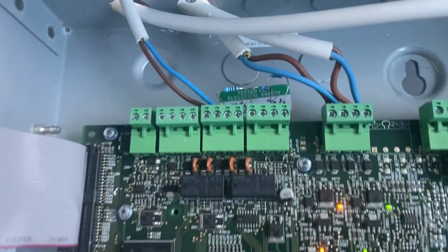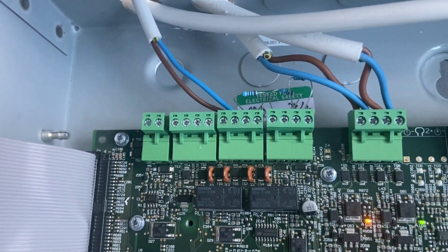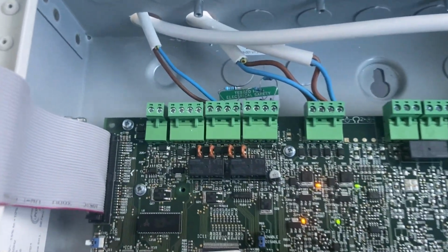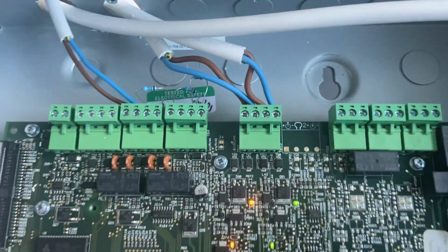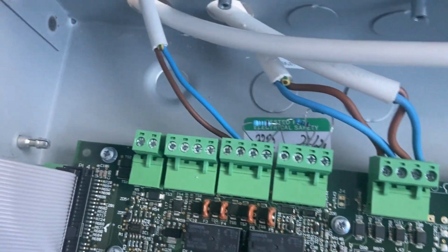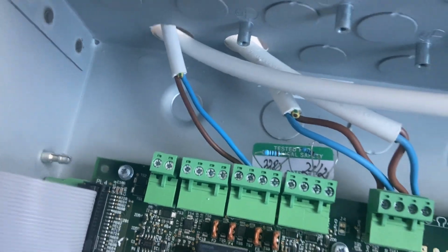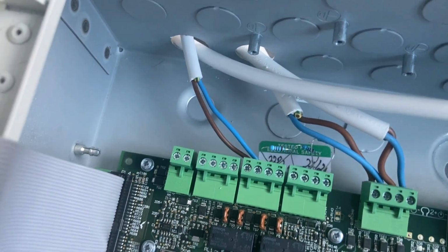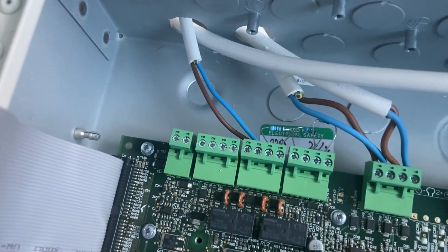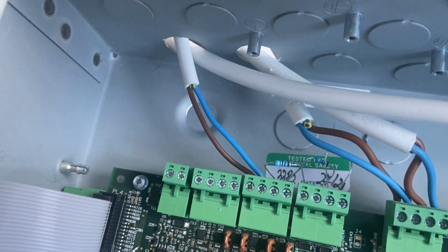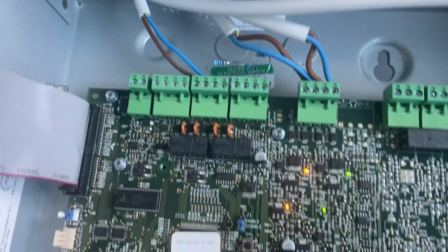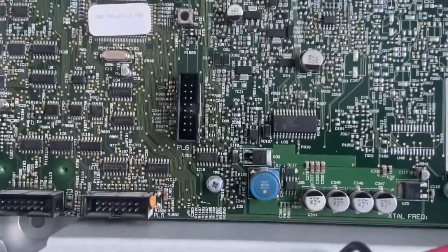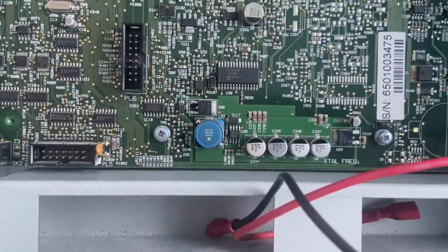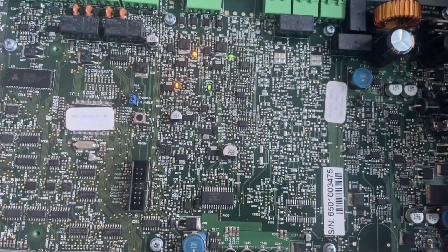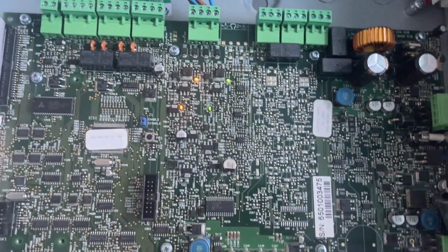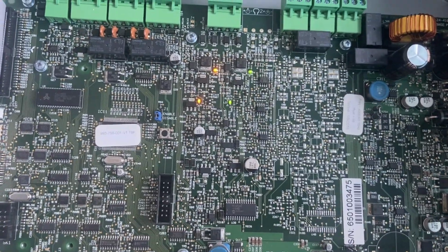So we've got the inputs and outputs and stuff on the other terminals, and then over here we have the loop wiring there. And then over here, that's extra wire there for a conventional sounder, because I have a conventional sounder hooked up to the system at the moment. So yeah, that wiring has a conventional sounder, and there we go. And then down here we have the battery wires. I haven't got a battery hooked up at the moment because that's where there's a battery fault. So yeah, that's basically it.